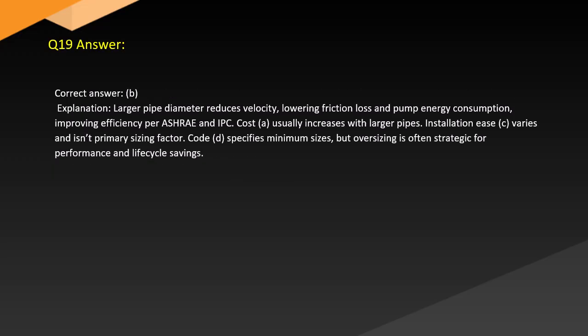Answer. Correct answer, B. Explanation. Larger pipe diameter reduces velocity, lowering friction loss and pump energy consumption, improving efficiency per ASHRAE and IPC. Cost, A, usually increases with larger pipes. Installation ease, C, varies and isn't the primary sizing factor. Code, D, specifies minimum sizes, but oversizing is often strategic for performance and life cycle savings.